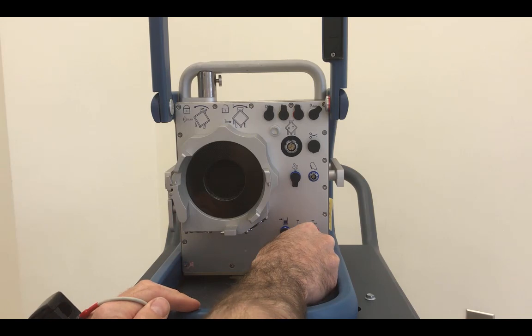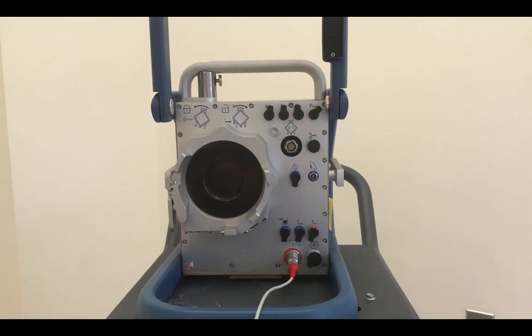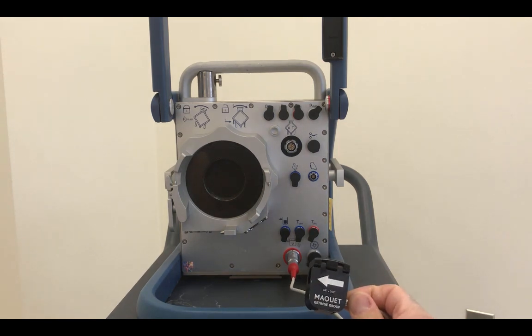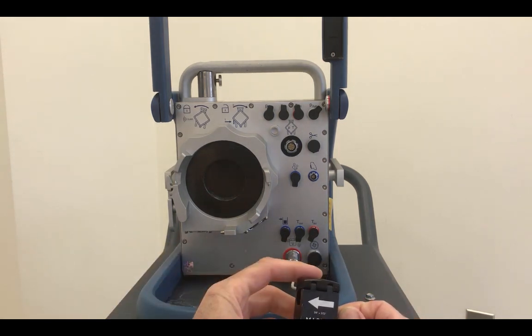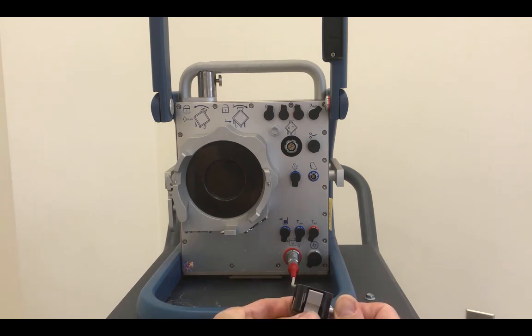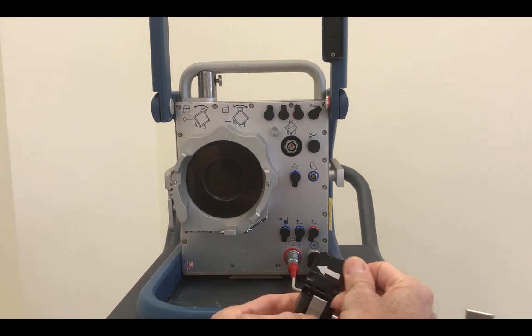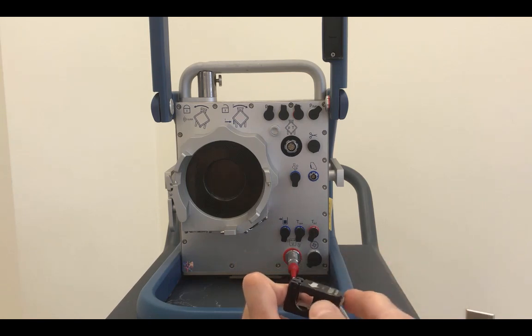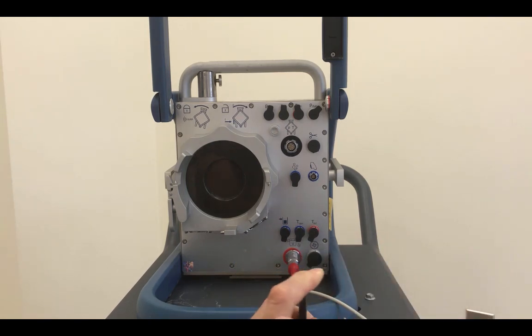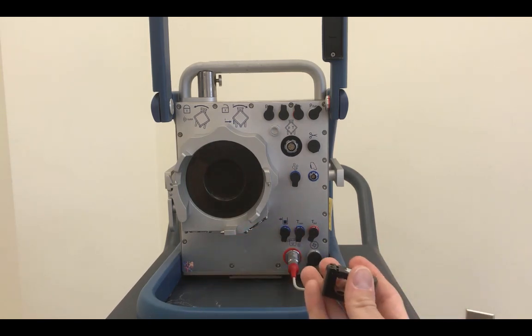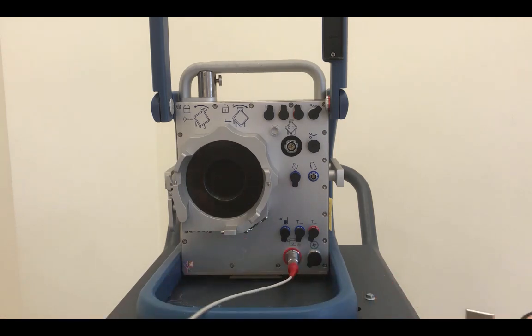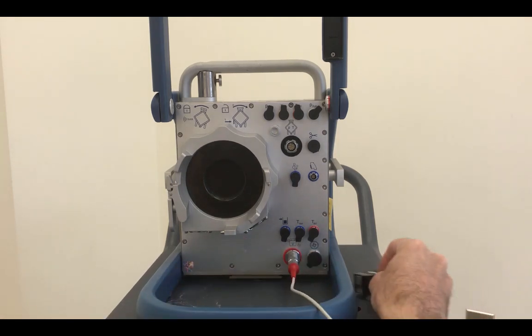So let's put the arterial bubble and flow probe, connect that in there. The other end of this line then would be connected to the arterial line. The arrow shows you the direction of flow. There's a lever here that opens the door. You put the 3/8 inch tubing through there, close that on it. We'll put that on later when we have a circuit on the pump.